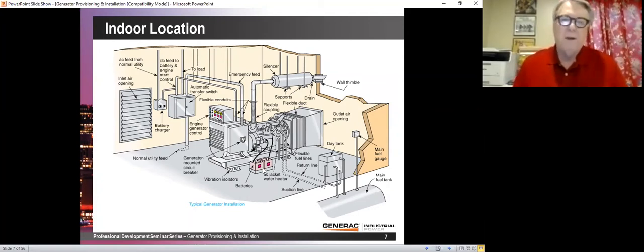Is that a good place for batteries? Well, obviously not. And I've never actually seen batteries that quite look like that. There are people that will have batteries in a battery rack, but you certainly don't want the batteries on the ground where they're going to get dirty and they could be subject to water if there were some kind of a flood. Generally, batteries are put on a battery rack that's permanently mounted to the generator. That's pretty standard. Then the batteries are up, really sitting on the generator. The battery cables are quite short, and that's a good place for batteries.